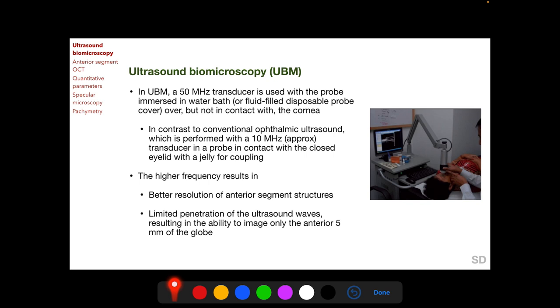In contrast, conventional ophthalmic ultrasound is performed with a 10 megahertz transducer, and during examination the probe is kept in contact with the closed eyelids with a jelly for coupling. During UBM, the eyelids are open, the probe does not contact the cornea, and water is used as a coupling medium. During conventional ophthalmic ultrasound, the eyelids are closed, the probe contacts the closed eyelid, and jelly is used for coupling.